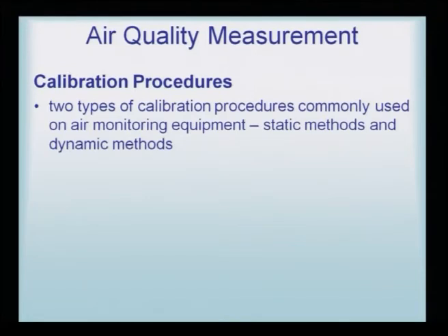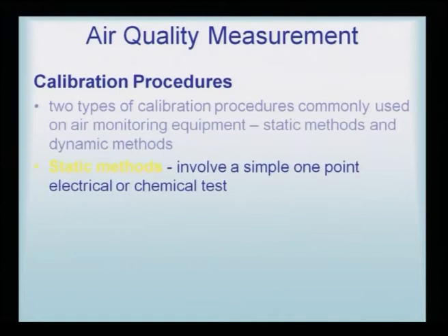Calibration process again, have two more important things to be told. Two types of calibration procedures mainly used on air monitoring equipment are the static methods and the dynamic methods. The static method involves a simple one-point electrical or chemical test, as the name suggests. It is just one air sample, some reagent may be added, and it is tested on the spot.